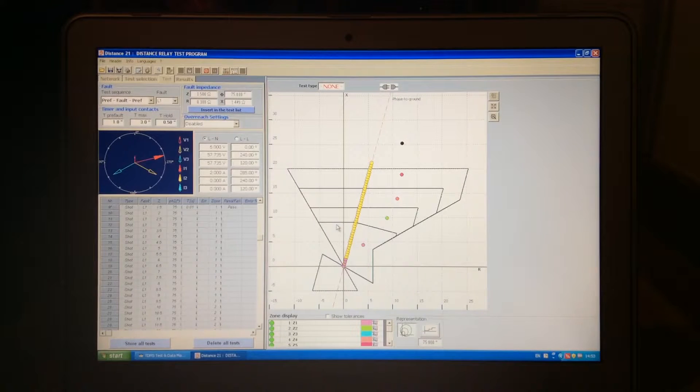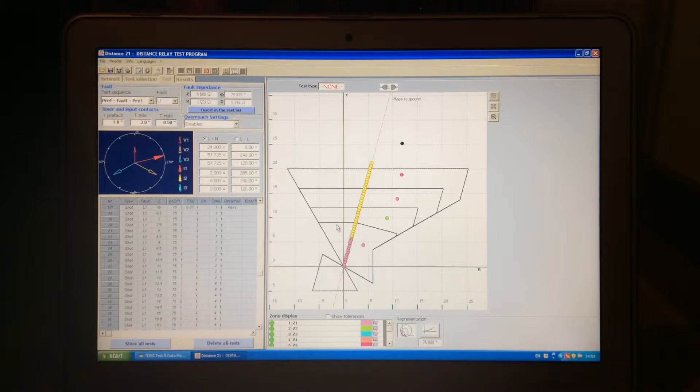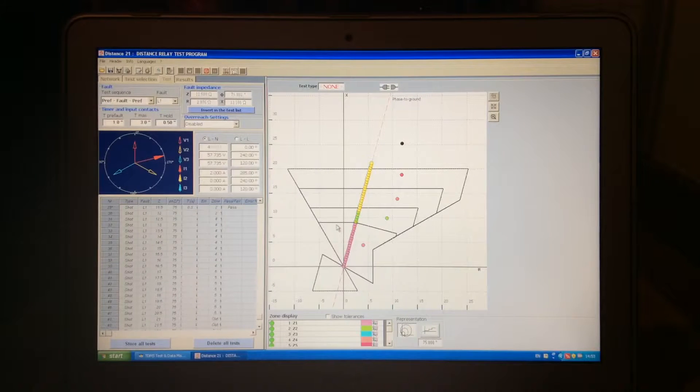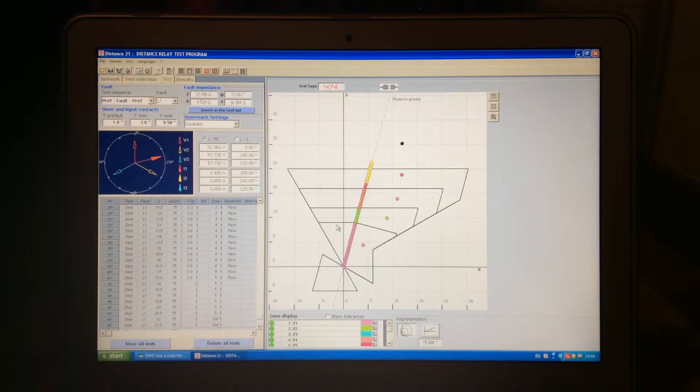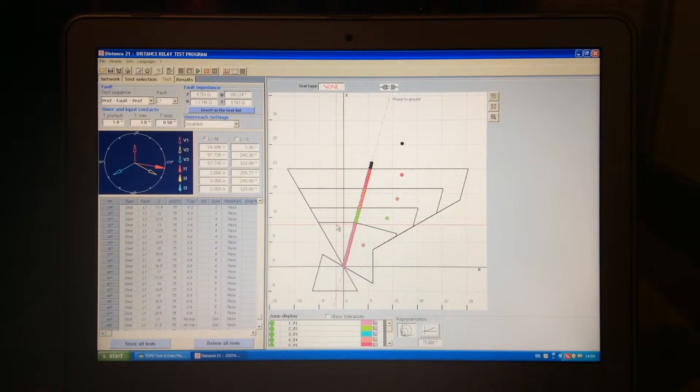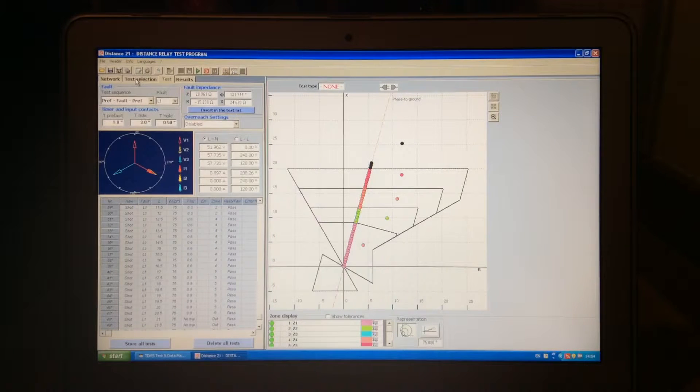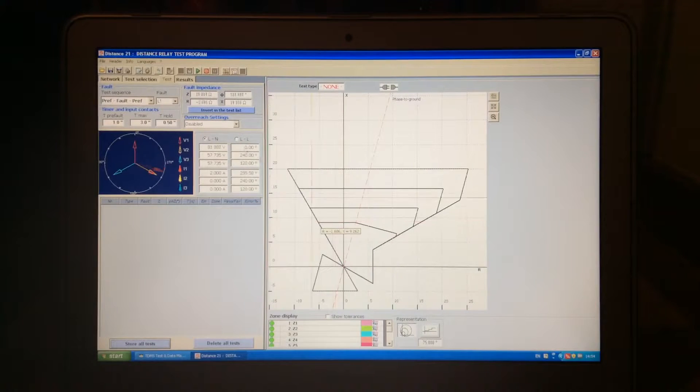So we'll be able to see how the RTS would be testing a distance relay for zone 1, 2, 4, 5, and outside. Once this is done, we can save the results. We first say store all tests, and we press yes.